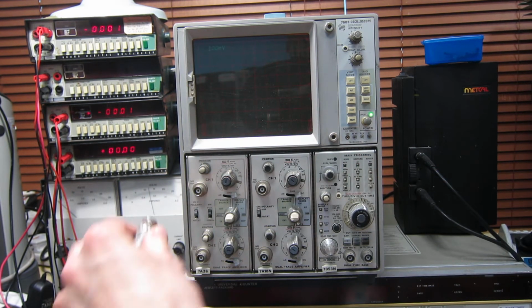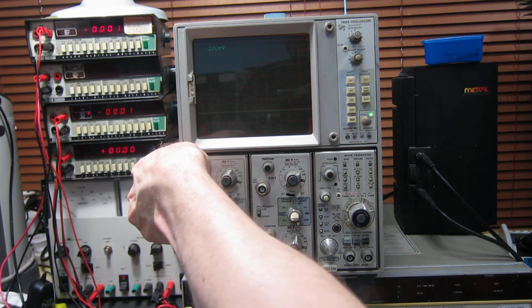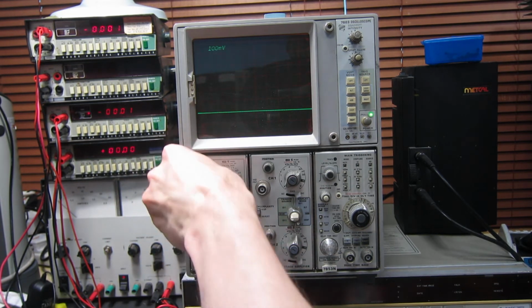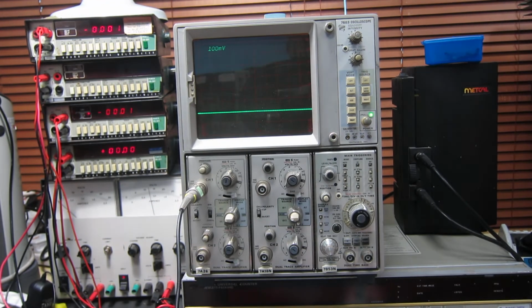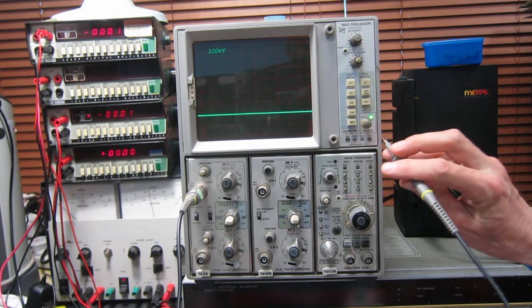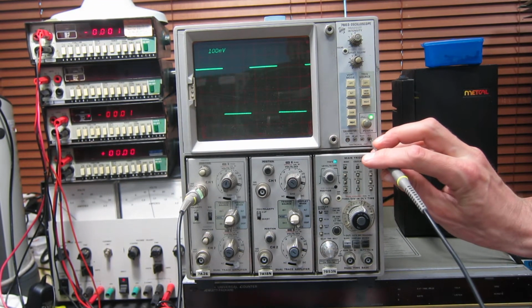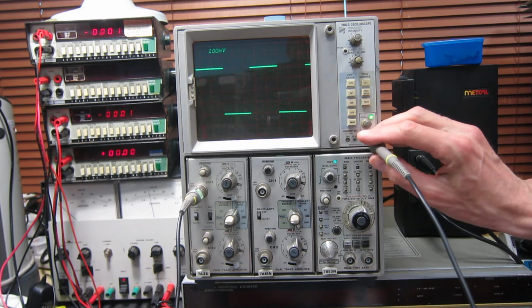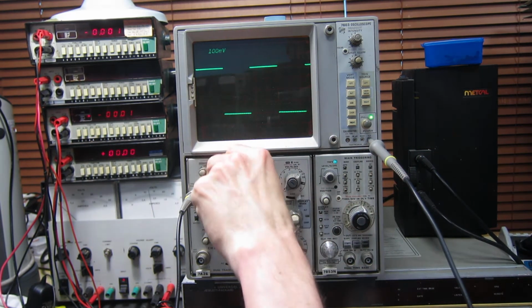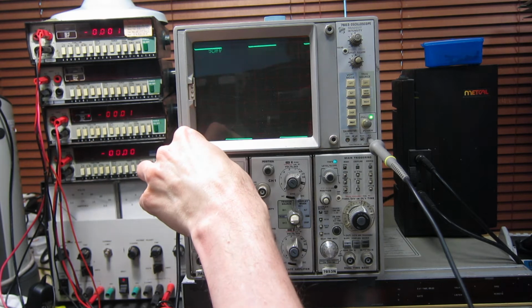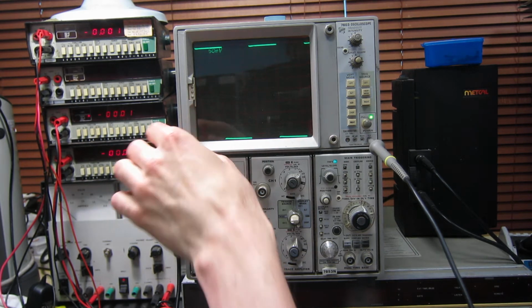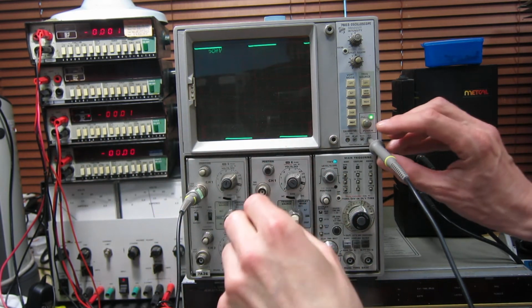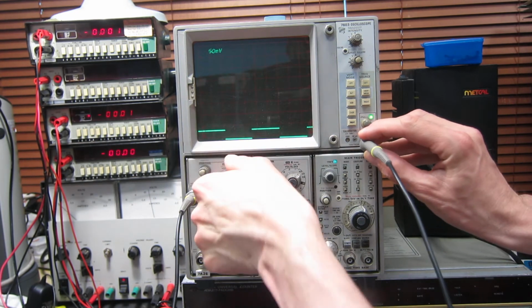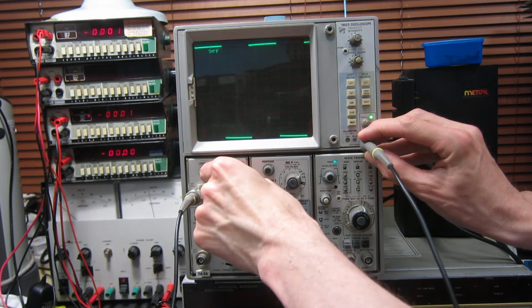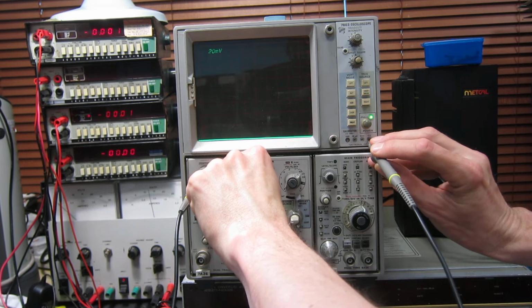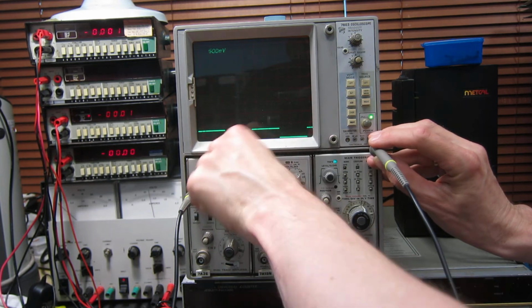I've got a scope probe set up here. Probe's not included, it's just something I'm using to test the equipment with. So we've got 100 millivolts per division. If I put that to ×10 probe in the calibrator there, you can see we've got 4 divisions, and I can increase that to 8 divisions. The adjustment's pretty good. I'll try the various different sensitivities. You can see it works through all the different attenuator settings as I go through there.